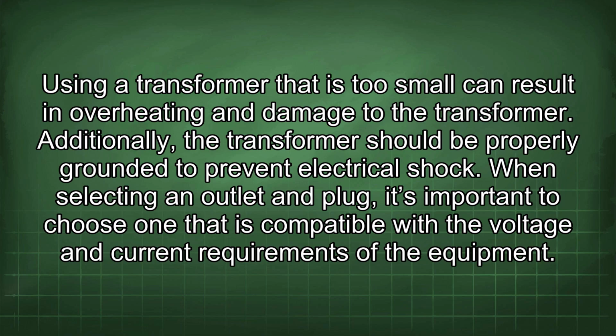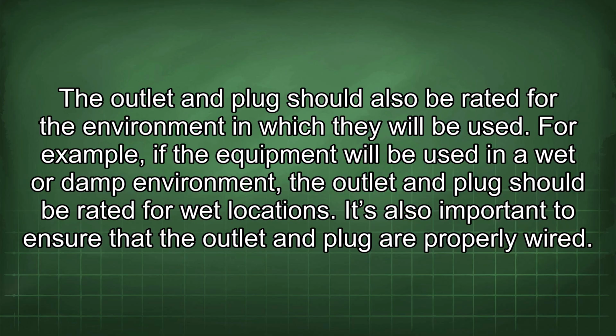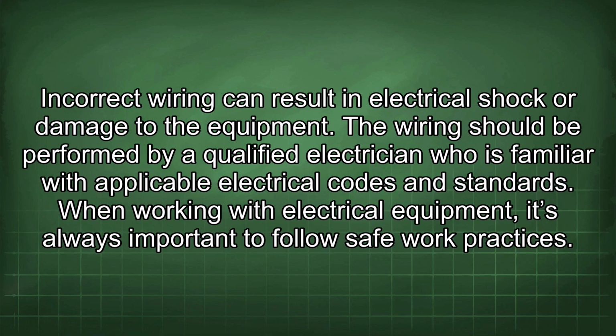When selecting an outlet and plug, it's important to choose one that is compatible with the voltage and current requirements of the equipment. The outlet and plug should also be rated for the environment in which they will be used. For example, if the equipment will be used in a wet or damp environment, the outlet and plug should be rated for wet locations. It's also important to ensure that the outlet and plug are properly wired. Incorrect wiring can result in electrical shock or damage to the equipment. The wiring should be performed by a qualified electrician who is familiar with applicable electrical codes and standards.